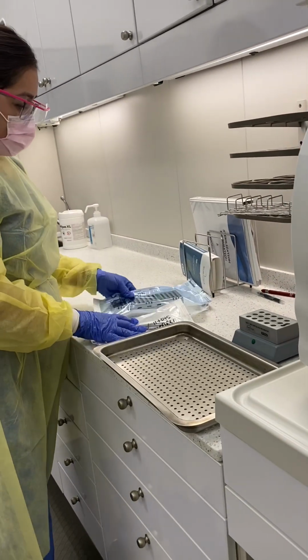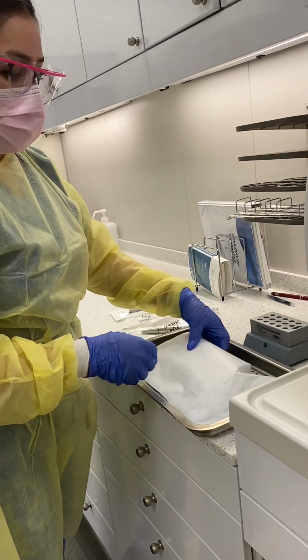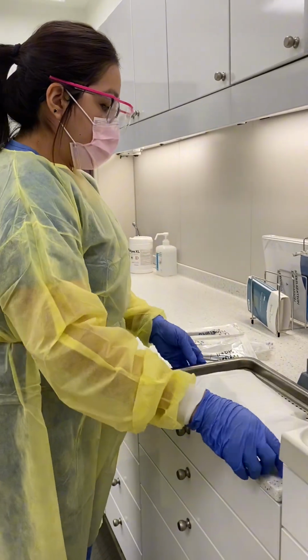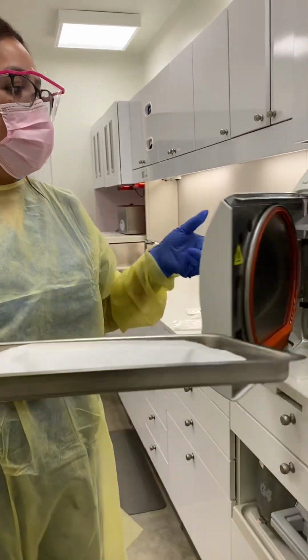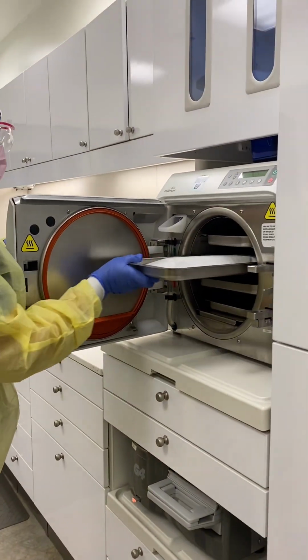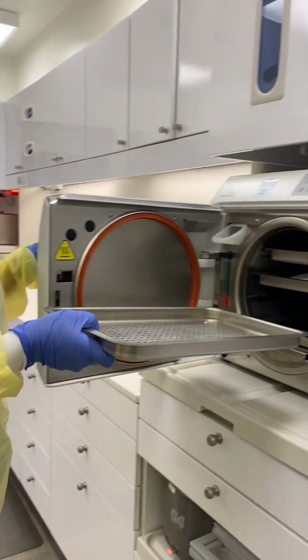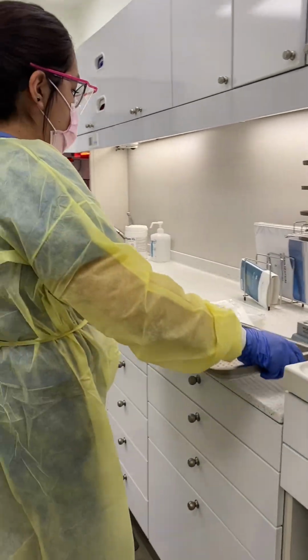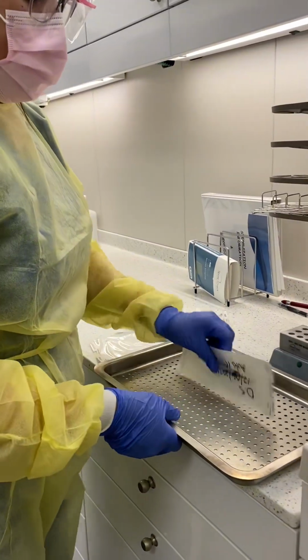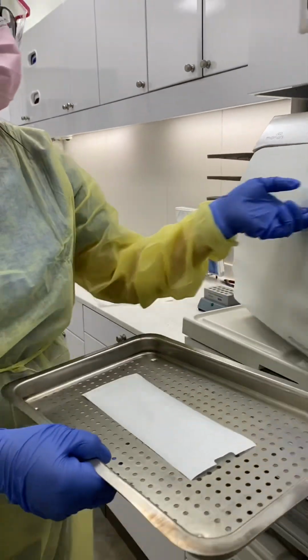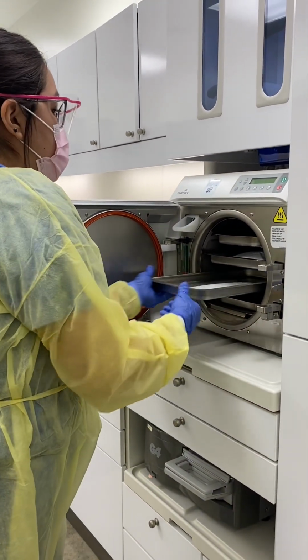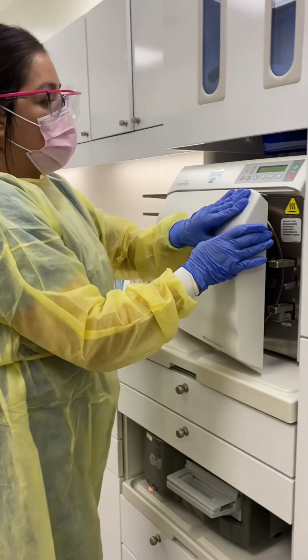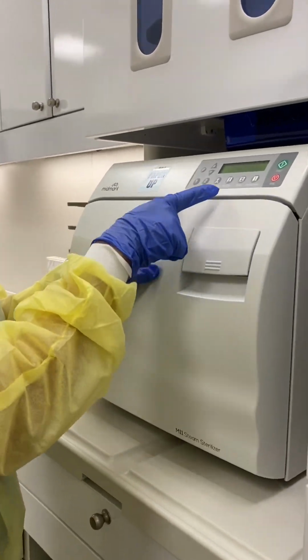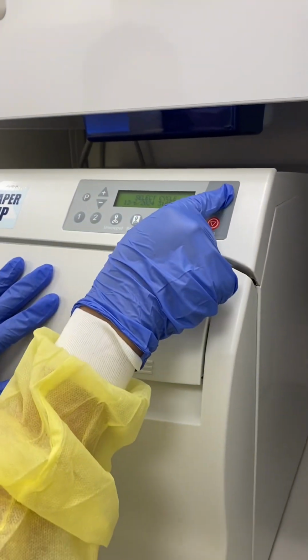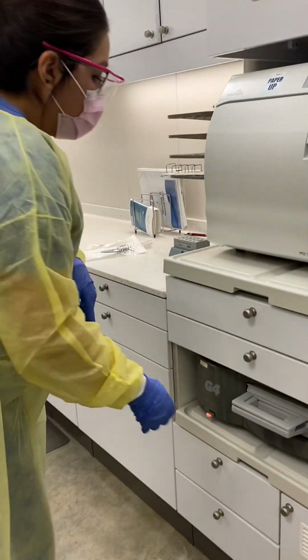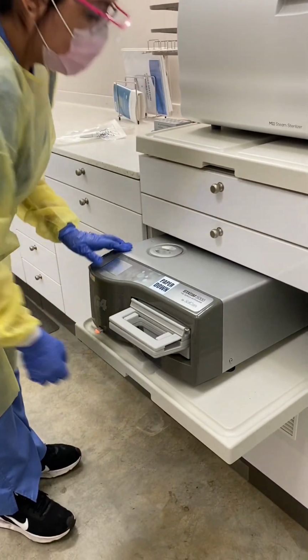Now we're going to put our loose pieces and cassette in our tray, paper side up. Remember not to overstack any instruments on top of each other. Simply grab another tray and put the remaining instruments there. To run the autoclave, we need to close the door properly, hit the pouch button, and hit the start button to run the cycle.